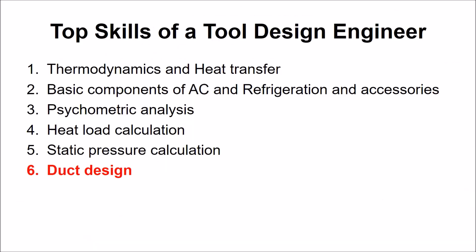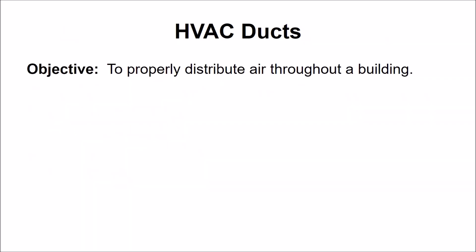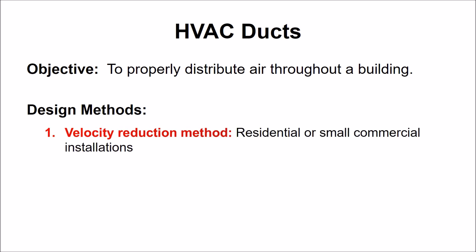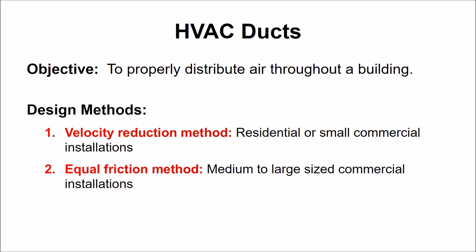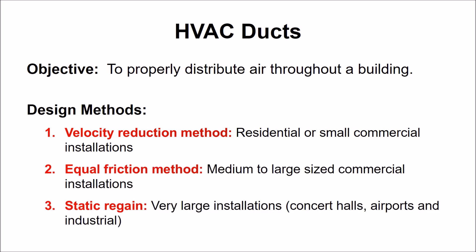Sixth skill is duct design. Duct systems are designed to properly distribute air throughout a building. Ducts that are not well designed result in discomfort, high energy costs, bad air quality, and increased noise levels. There are many different methods used to design ventilation systems, the most common being the velocity reduction method, equal friction method, and static regain method. Choosing the right size duct is critical to maintain proper airflow in the system.